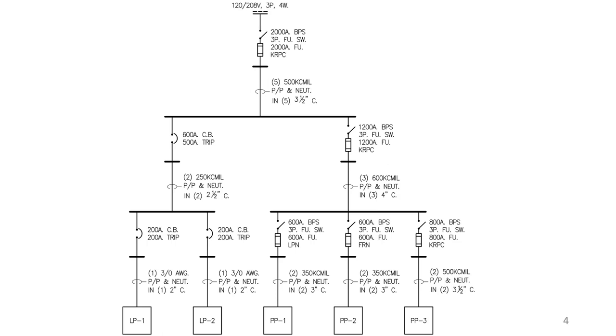However, traditionally, fuses have been able to selectively coordinate 2-to-1, which is published information from manufacturers. Circuit breakers is not that easy. So even though the available fault current is low, most people still go with fuses. It's a common industry practice, especially in our neck of the woods. It may be different in other parts of the country. But up here in New York City, most jobs, they're using service disconnect with fused switches.